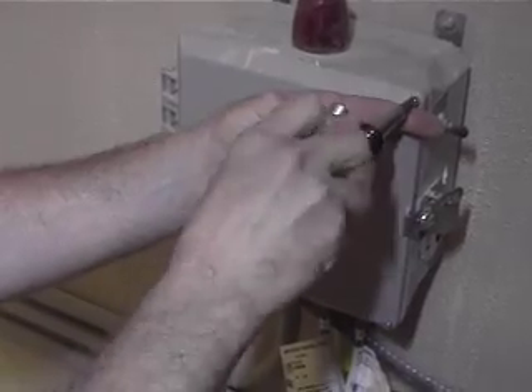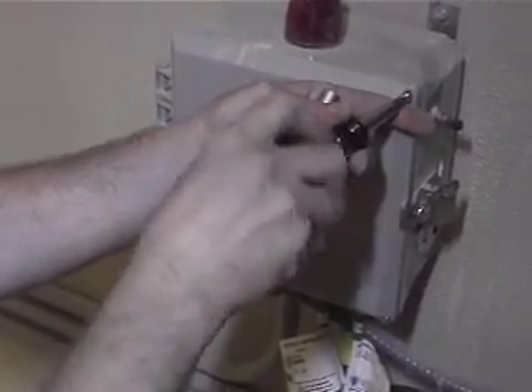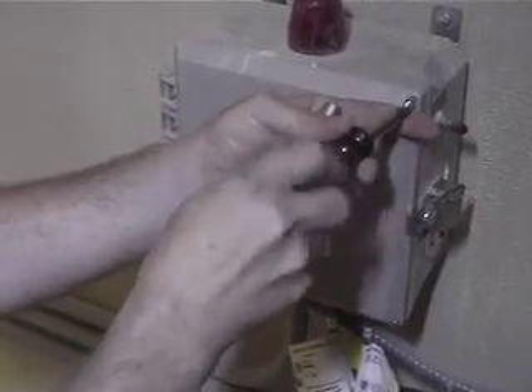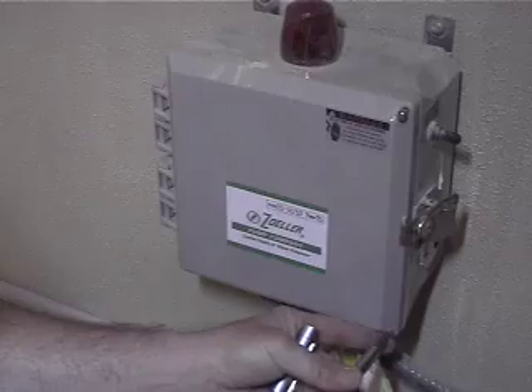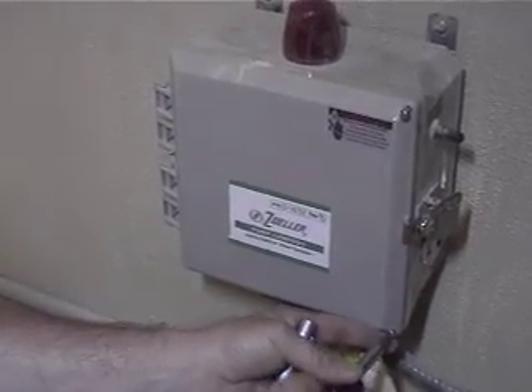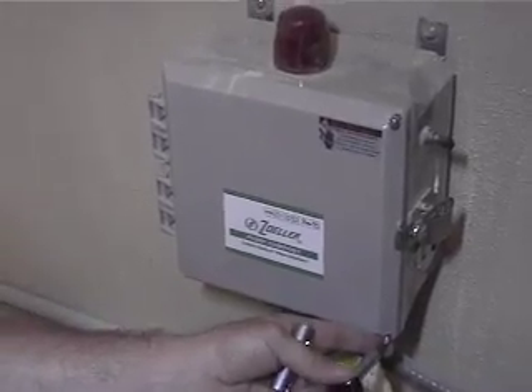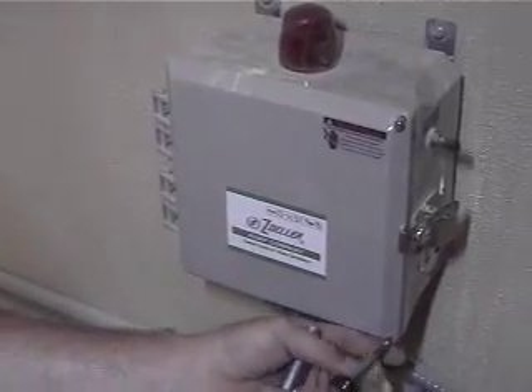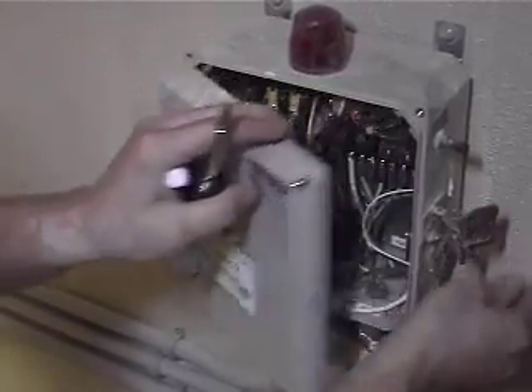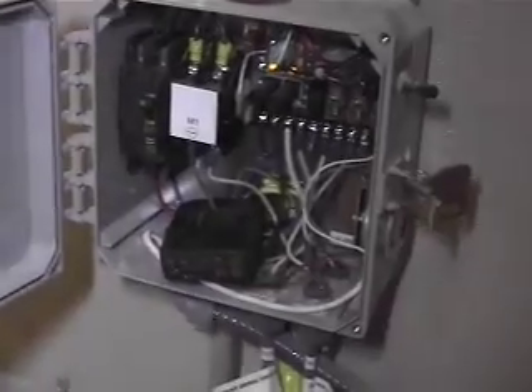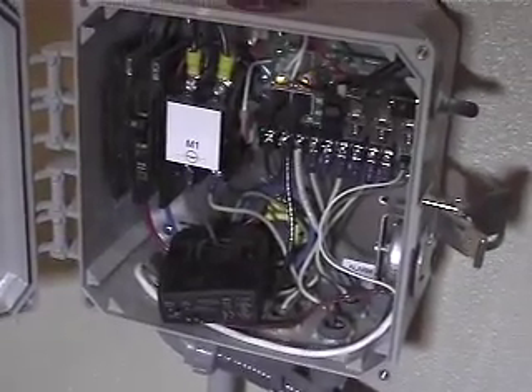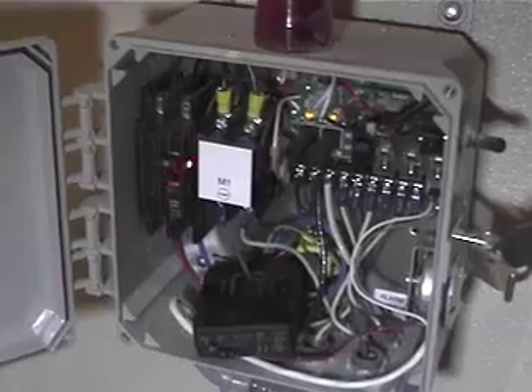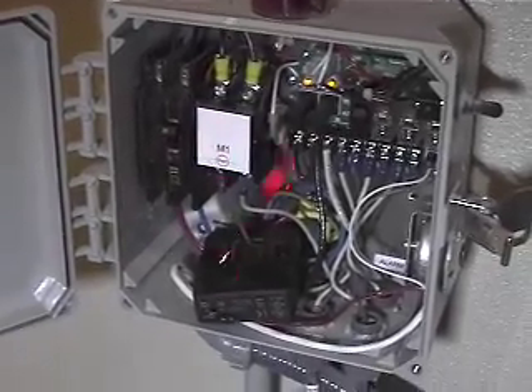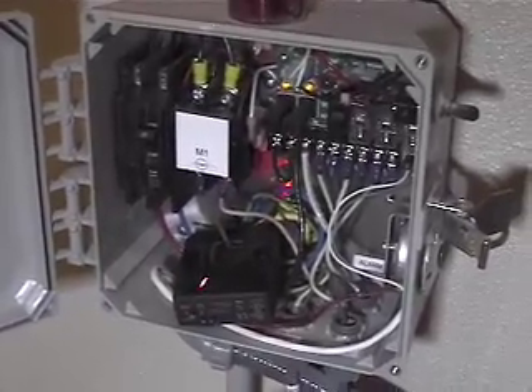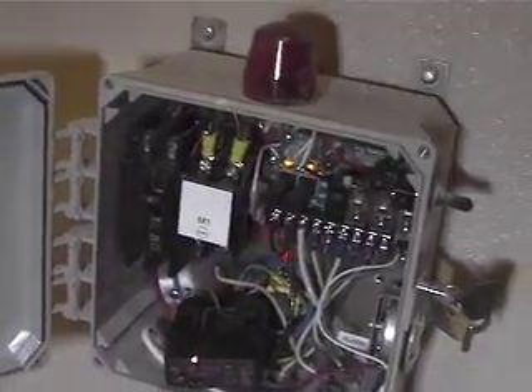Inside this control panel, sorry, it'll take me a second to get this open. It's got the two screws, one on top, one on bottom, and a latch on the side. The building control system does monitor these pumps. If these pumps come on, it does let the building management system know that these pumps had come on. So that could be an indication to you that this thing did have to fire up. Inside this control panel, there is a circuit breaker here for our pumps. This is the contactor for our pump. This CT is what lets the building automation system know that the pump is running.